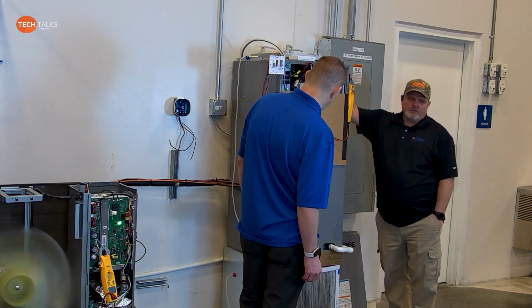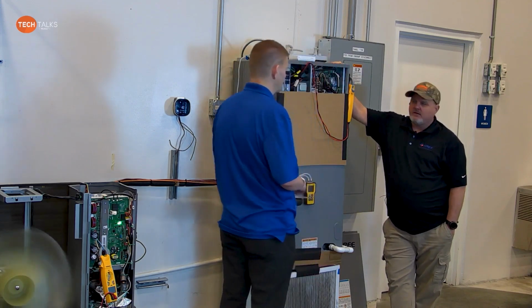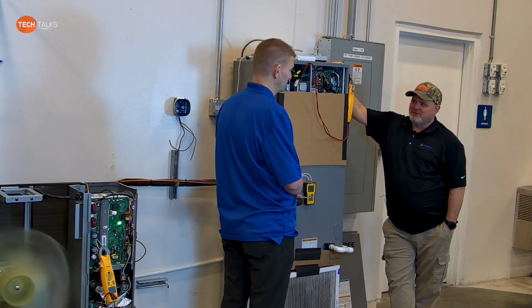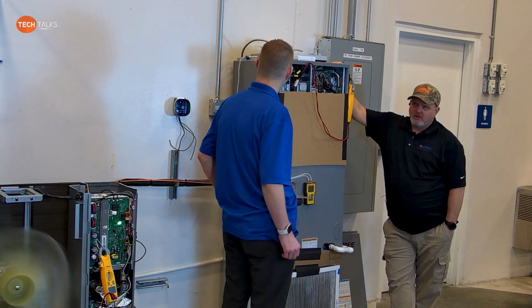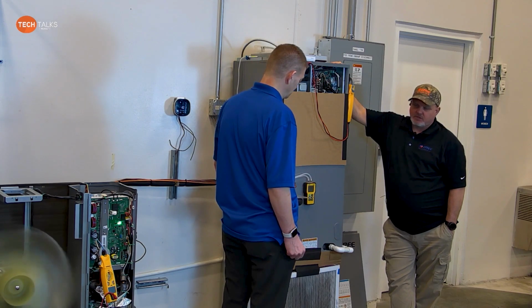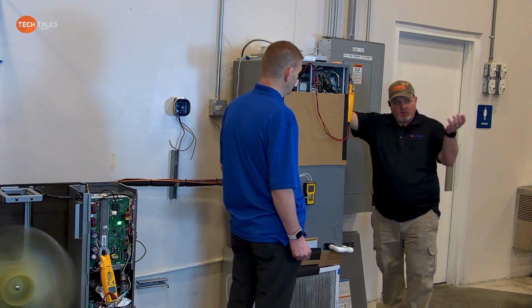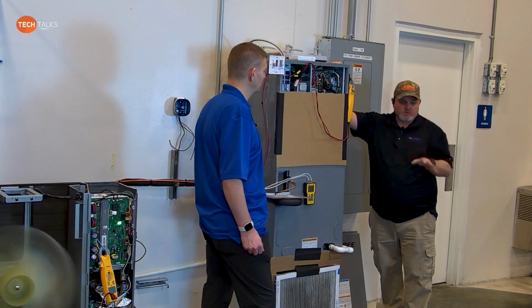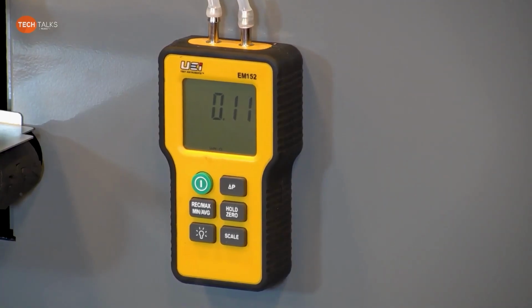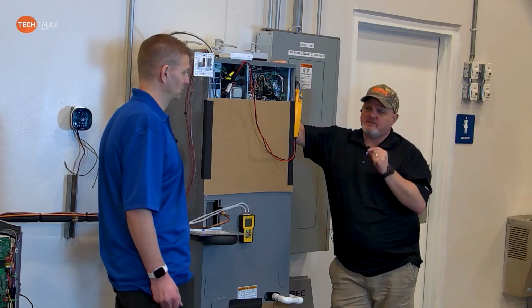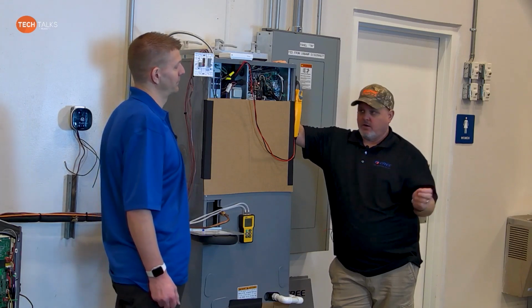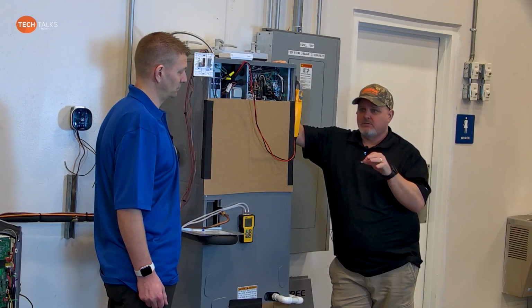Now, one thing I want to mention to the audience is, guys, this is a lab unit. I don't have ductwork and everything on it. When you're doing this out in the field, it's going to be completely different. But the importance of verifying the static pressure. Let's talk about static pressure a minute, and then I'll go back to the static pressure charts. Even if you use the GREE controller, I told you guys you don't have to set the dip switch profile because it comes more as a variable speed operation. But keep in mind, you still got to make sure that this thing's not running against high static. An ECM blower pushing against high static is a motor killer. I don't care who makes it. You can't just expect an ECM motor to overcome high static.